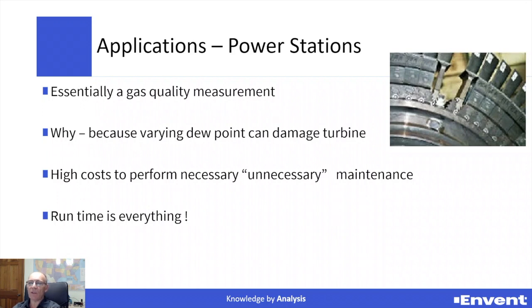They can be significantly different, and gas-fired power stations have what's called a superheat capability, to provide the gas additional heat to ensure it's wholly gaseous before it passes into the burn chamber and then onto the turbine to power the turbine. So if the superheat is not vaporizing all of the liquids, or if there are any liquids in the burn chamber and it's not being burnt efficiently, then the resultant wear can be seen on the turbine in the image on the right hand side.